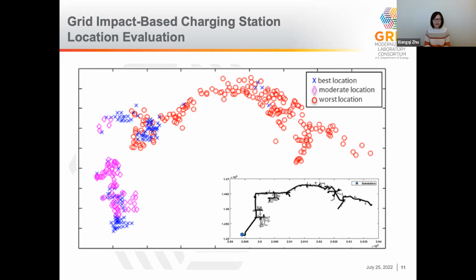The blue marks are the best locations with minimum voltage impact to the grid. The diamond-shaped dots represent good or moderate locations, which can host some high-capacity charging stations but not many. The remaining circled red ones are the worst locations—some can host lower charging rate stations, while others would cause voltage violations if hosting charging loads, meaning without mitigation solutions those nodes cannot host charging stations.